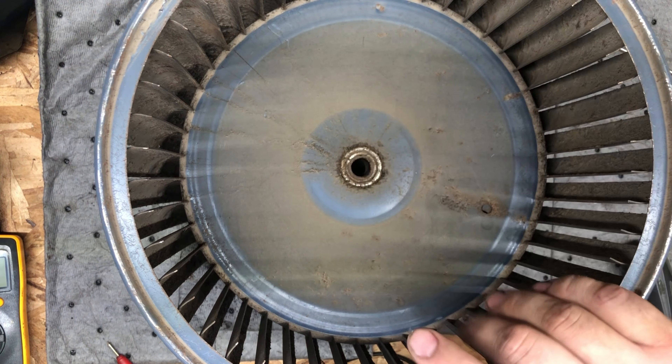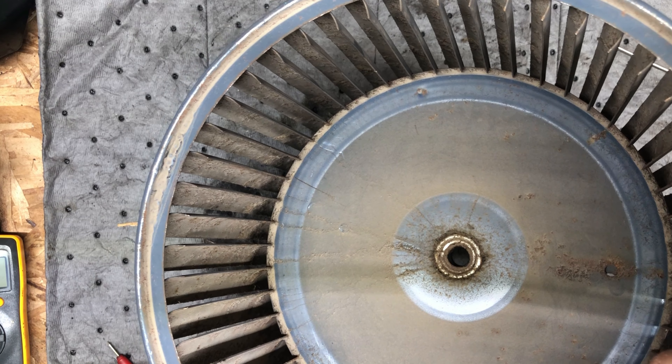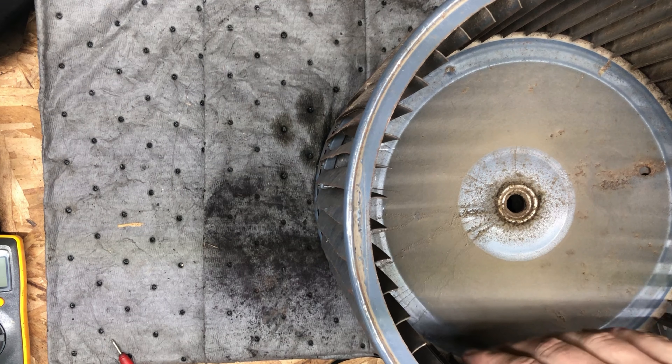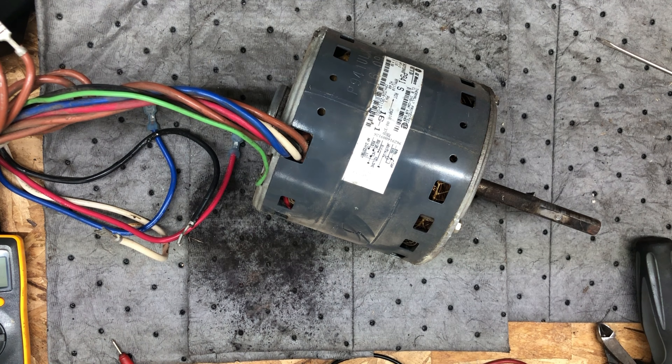You can see it kind of pitting on the inside there, which I guess would be part of the rusting I just mentioned. The rust forming in there — who knows. This could have been out of balance, or more likely the bearings were on their way out.